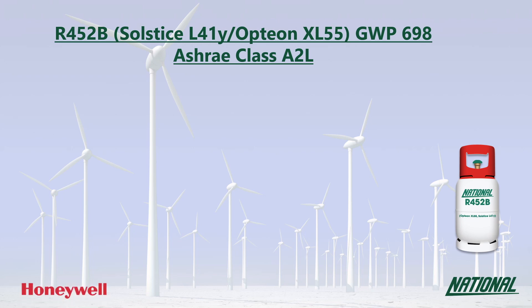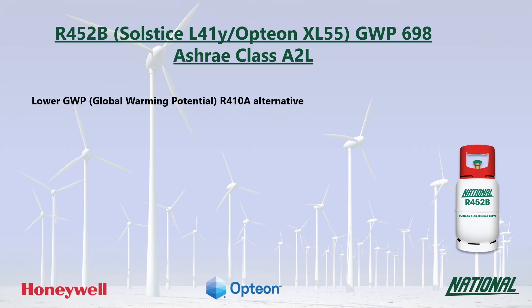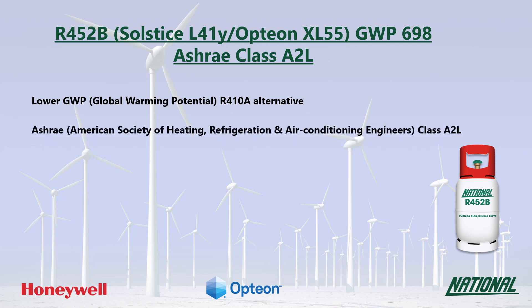R452B was developed by Honeywell and Chemours as a lower GWP alternative to R410A. You may also see it referred to by its manufacturer's trade name Solstice L41Y and Opteon XL55. Its GWP is 698, so at a third of the GWP of R410A, it is a much more environmentally friendly option and has been classified by ASHRAE as A2L, mildly flammable.